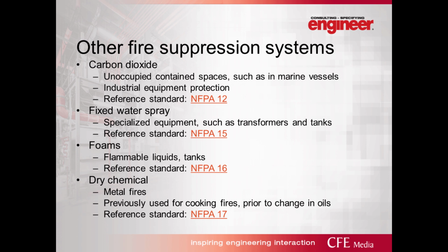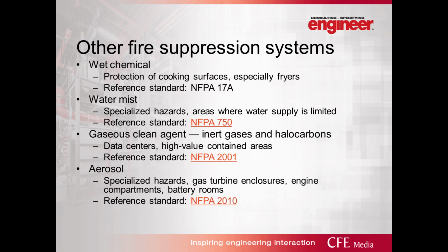Dry chemical systems are good for metal fires. If you run into a metal fire hazard, dry chemical is something that you really should consider. Many of you that have been around for a while may recognize that dry chemical systems used to be used for protection of cooking equipment. However, oils have gotten better but worse, and the dry chemical systems actually can't deal with the higher temperatures that cooking oils now burn at. Wet chemical systems are now the agent of choice for protection of commercial cooking surfaces, especially fryers that use these newer oils.